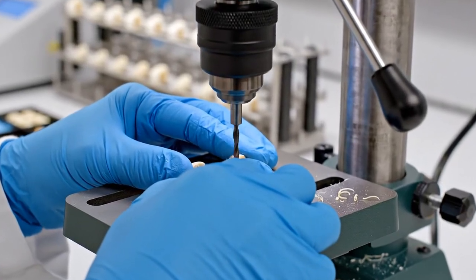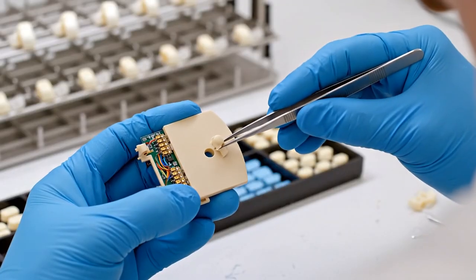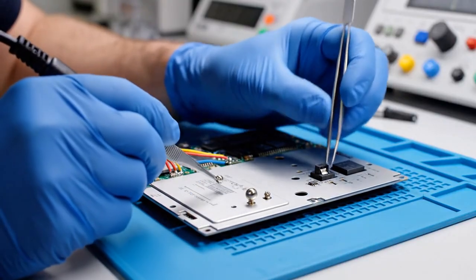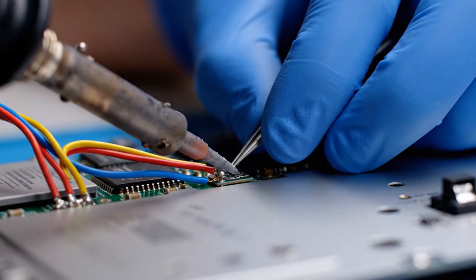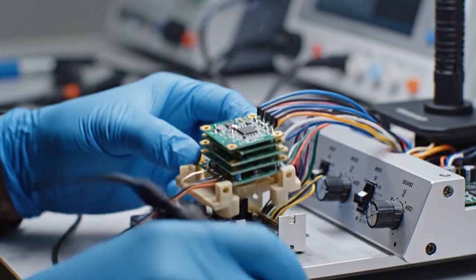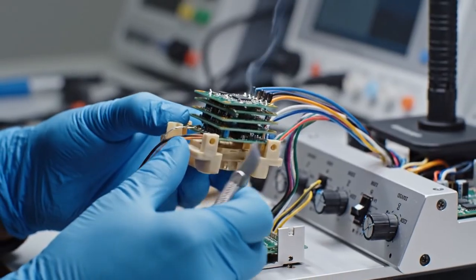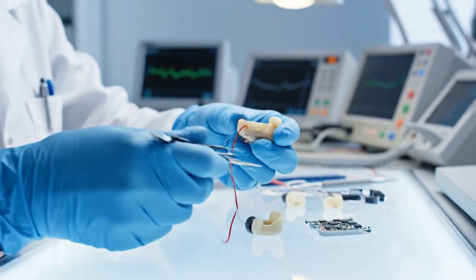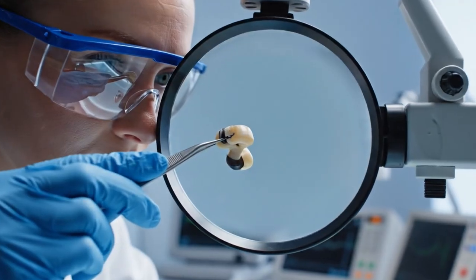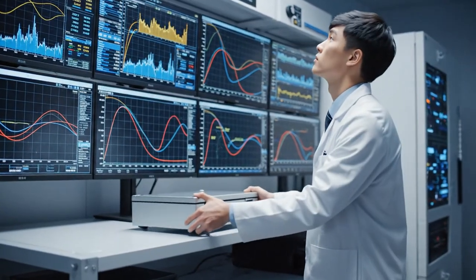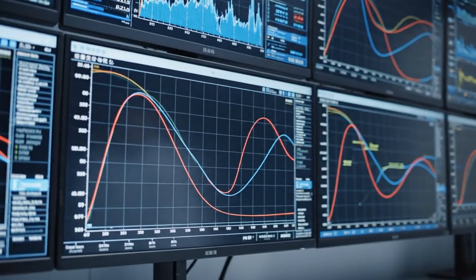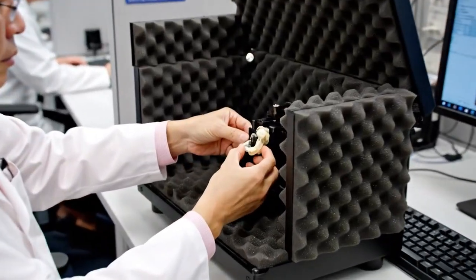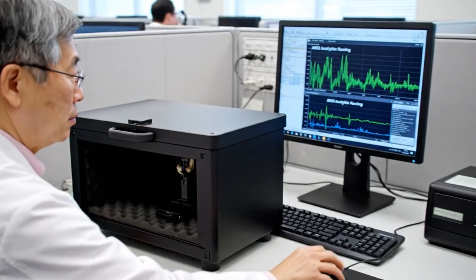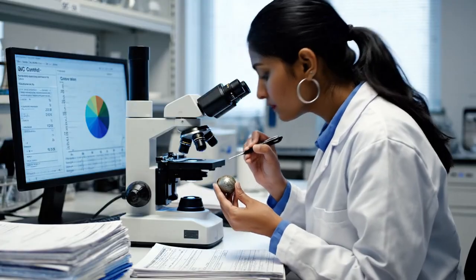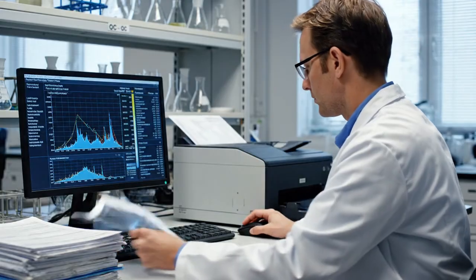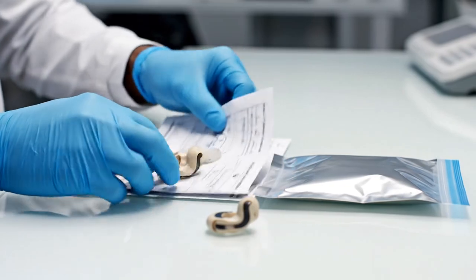The technician assembles the electronic hardware on the faceplate, where holes have been drilled for mounting the microphone, amplifier, battery compartment, and volume control, all hand-wired with colors for traceability. The wires are soldered into place. After this, the receiver is mounted into the shell, and a preliminary hearing check is made on the instrument. Rigorous quality control measures are implemented throughout the manufacturing process. Various tests are conducted to ensure quality. Hearing aids are also tested using a computerized ANSI, American National Standards Institute program, that analyzes the production parameters and produces a performance chart. A technician reviews the chart on screen, checking tolerance levels and other specifications of the results, and includes it with the finished hearing aid.